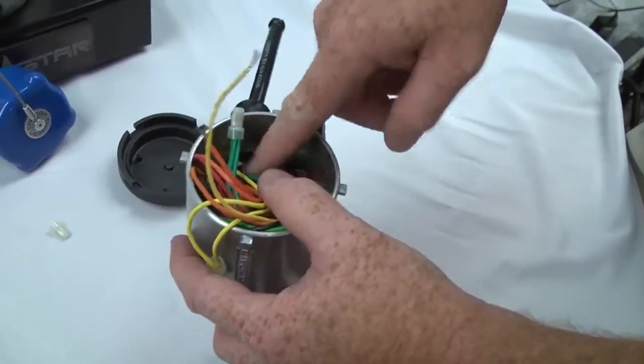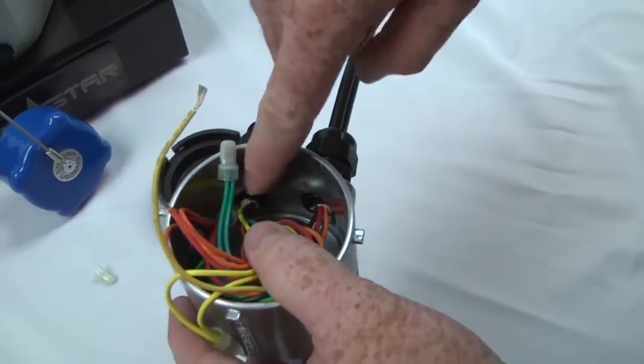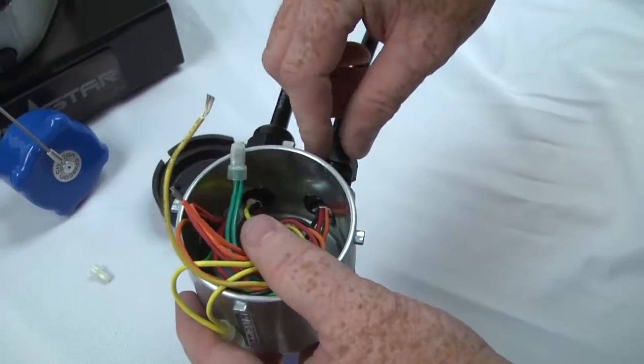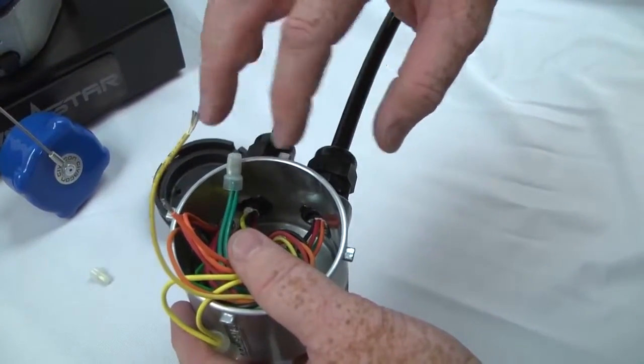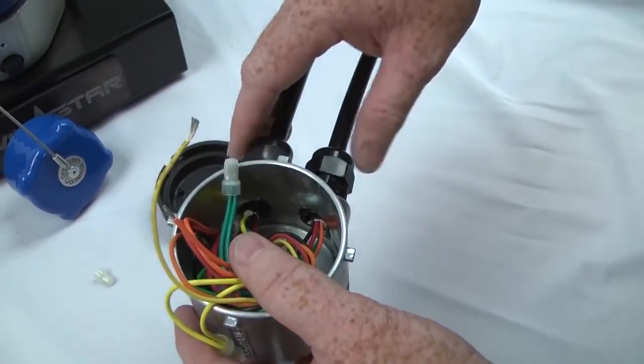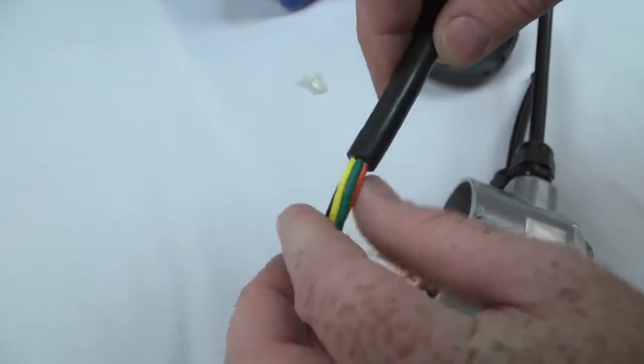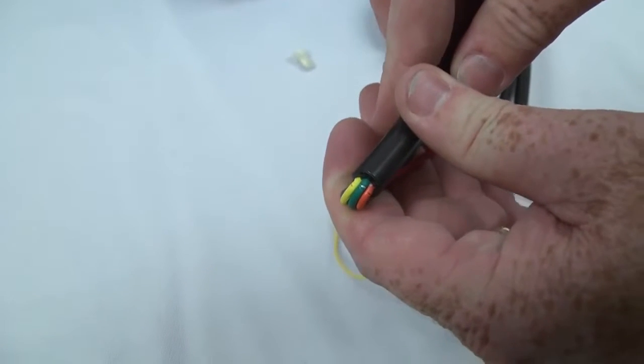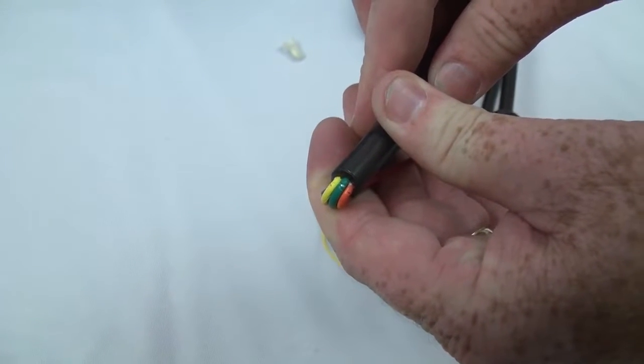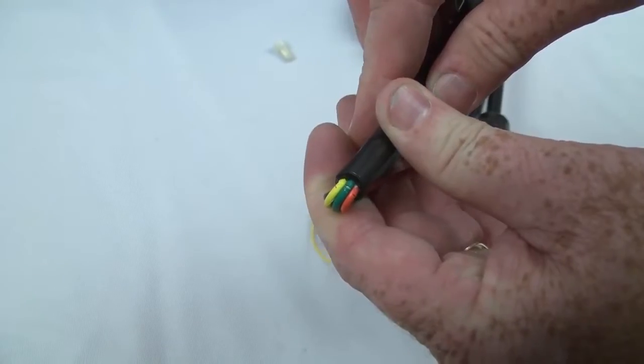Also pay close attention to where the outer cabling is stripped off of each wire where it goes through the strain relief fittings. This is also at each probe housing and at the socket itself. If the outer casing is improperly stripped, the inner wires can be nicked, allowing a place for moisture to get in and corrosion to form.